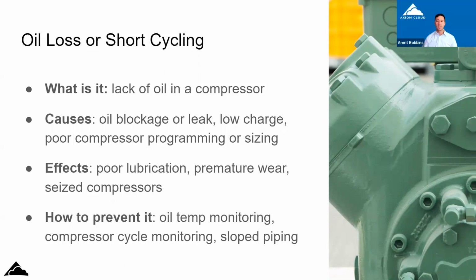Makes sense. Joe, have you seen a recent example of this out in the field? Oil loss. All the time. Oil is just one of those tricky things where there are so many different things that can cause it, from the oil system not working, like Trevor said, floodback coming in, hitting the compressor, cycle rates. Oil is probably the hardest thing to troubleshoot on a compressor when it's not happening, because there are just so many factors in it. Where does it sit on the bench? Just so much comes into play.